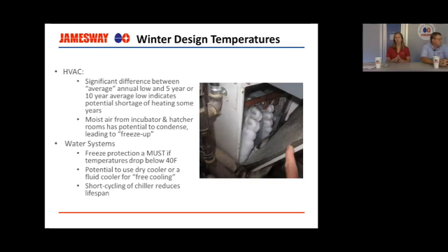One of the other problems we have is that because we're running our incubator and hatchery rooms at a higher relative humidity than you would run an industrial or a commercial or even a residential building, that humid air goes up into the rooftop and it mixes with the cold outside air. And sometimes we drop below dew point, so that means that dew or condensation is formed. And that forms, as you can see here, right on the coils.